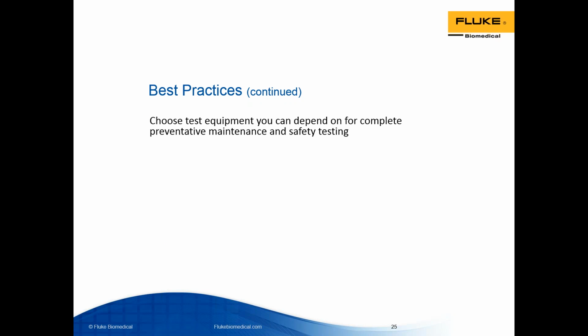Finally, choose test equipment that you can depend on for full preventative maintenance. You need to use separate equipment. Some incubators, for example, will have a self-check in them, but you need to use separate equipment because, as specified by regulatory bodies such as the FDA, independent objective evidence for parameters that you measure is required. When choosing your instruments, remember that metrology matters.